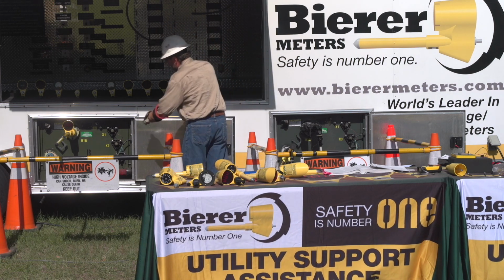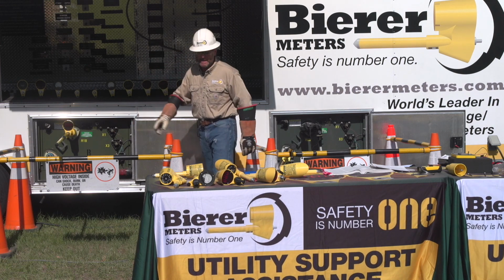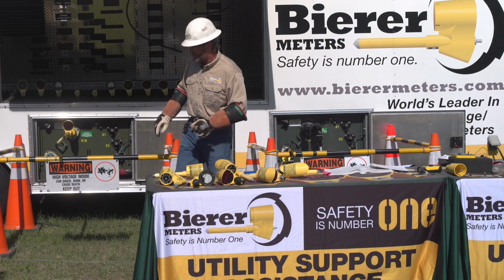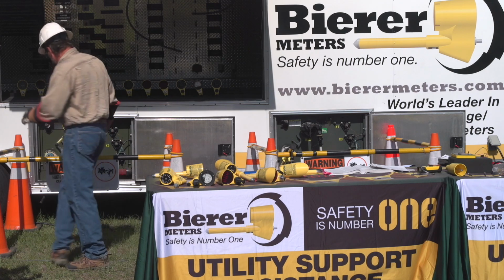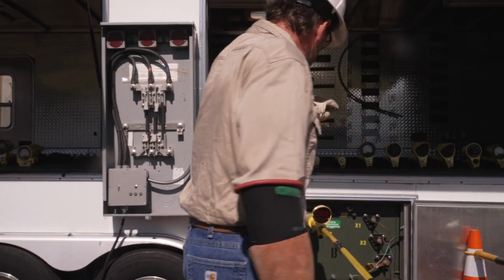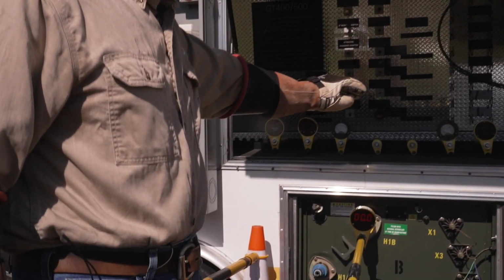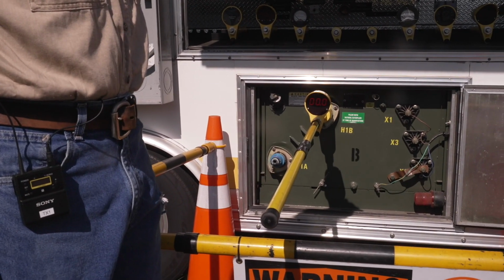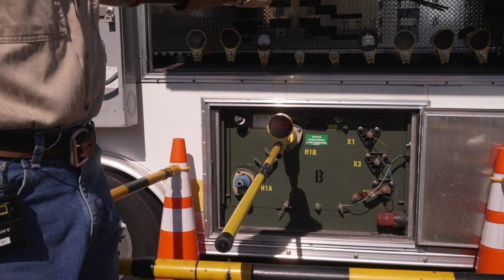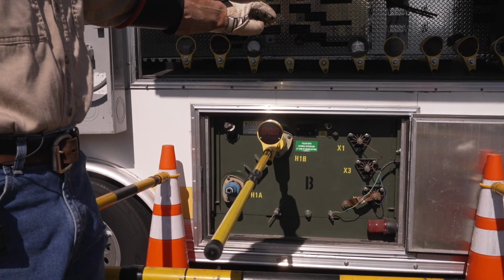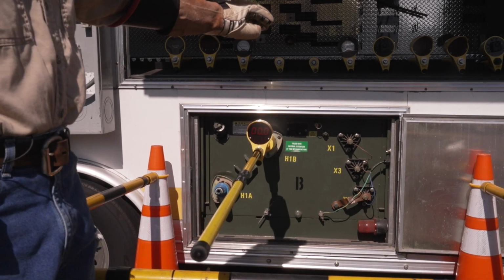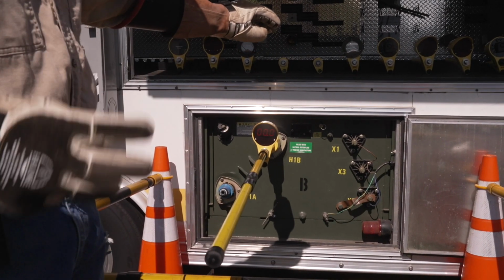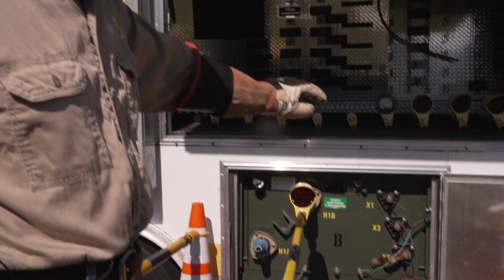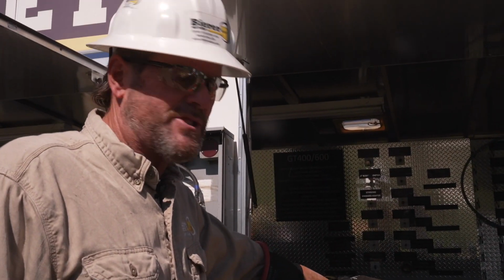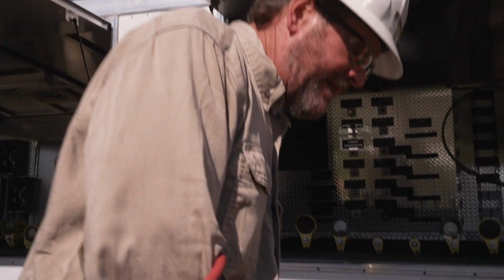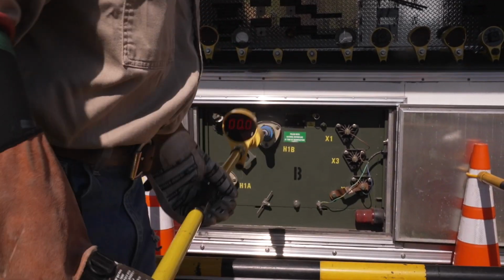So we come back on this overhead line and just do a test real quick. You can see the tool is telling us that we do not have any nominal voltage. Our system voltage is gone. The tool is accurate enough that we don't see any induction and we don't see any backfeed. We're always going to check an absence of all three. I think this in the OSHA regs needs to be changed, I really do. So then that's number three.